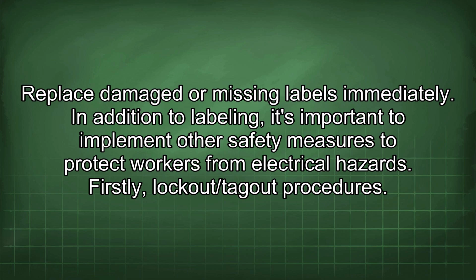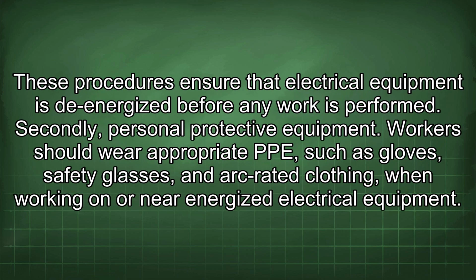In addition to labeling, it's important to implement other safety measures to protect workers from electrical hazards. Firstly, lockout/tagout procedures, which ensure that electrical equipment is de-energized before any work is performed. Secondly, personal protective equipment: workers should wear appropriate PPE, such as gloves, safety glasses, and arc-rated clothing when working on or near energized electrical equipment.